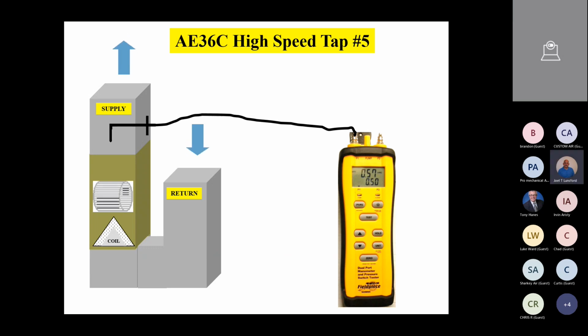And so we notice that on the supply side, we've got 0.57 inches of water column, which is pretty high. So go ahead and write that down or make a note of it, 0.57. And fellas, you're going to notice something too. Another reason to take these pressures individually is it helps you figure out where your problem is on the ductwork. By taking the supply and return pressures individually, it can help us break down which side of the fan we are having issues with, the supply side or the return side.